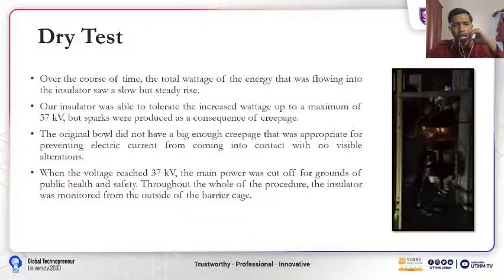Our insulator was able to tolerate the increased voltage up to a maximum of 37 kV, but sparks were produced as a consequence of creepage. The original bowl did not have a big enough creepage distance to prevent electric current from coming into contact, with no visible alteration. When the voltage reached 37 kV, the main power was cut off on grounds of public health and safety. Throughout the whole procedure, the insulator was monitored from the outside of the barrier cage.